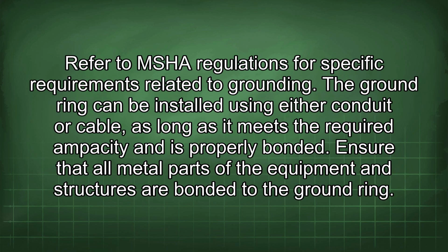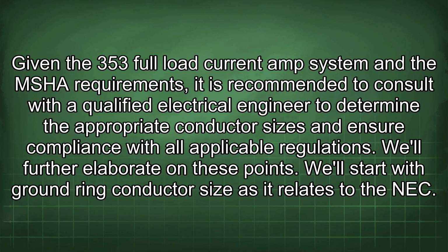We refer to MSHA regulations for specific requirements related to grounding. The ground ring can be installed using either conduit or cable, as long as it meets the required ampacity and is properly bonded. Ensure that all metal parts of the equipment and structures are bonded to the ground ring. Given the 353 full load current amp system and the MSHA requirements, it is recommended to consult with a qualified electrical engineer to determine the appropriate conductor sizes and ensure compliance with all applicable regulations. We'll further elaborate on these points.